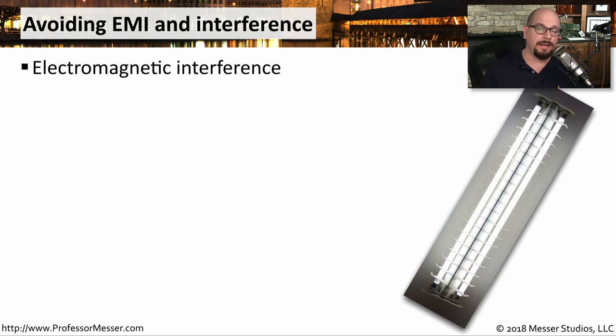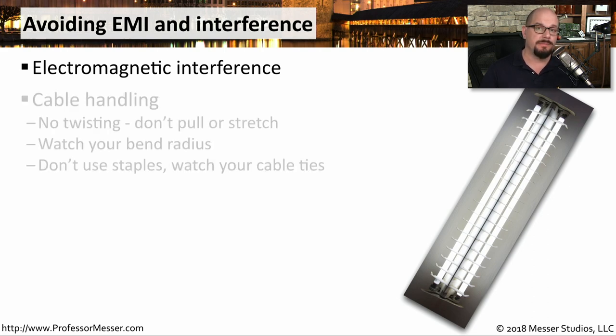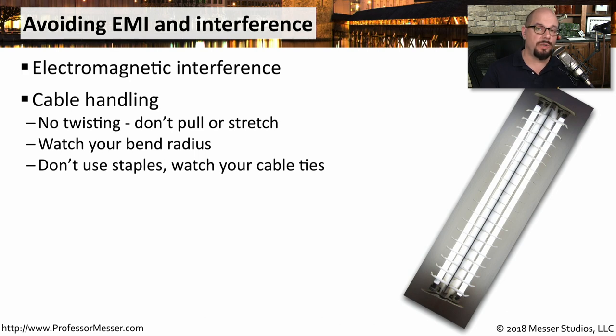EMI is electromagnetic interference. Our cables are not indestructible, and we want to be sure we're handling them properly and running them along areas where the EMI will be minimized. If you are running some new cables, you want to be sure not to twist them during installation and minimize the amount of pulling or stretching. You also want to be sure that you don't have any sharp bends — each cable will document the minimum bend radius allowed, and you don't want to exceed that. You also don't want to use staples or any type of cable ties that might crimp the wires inside of those cables.